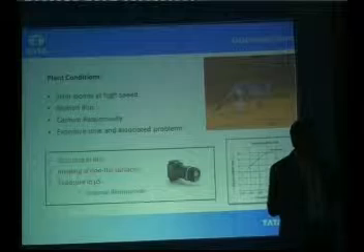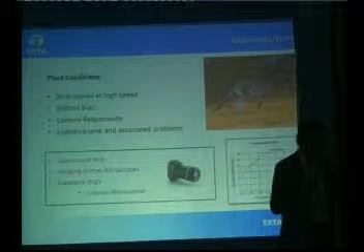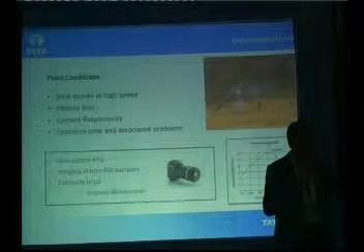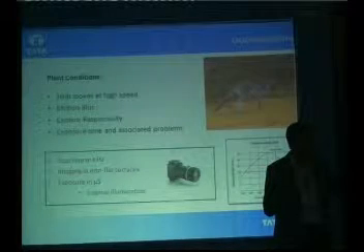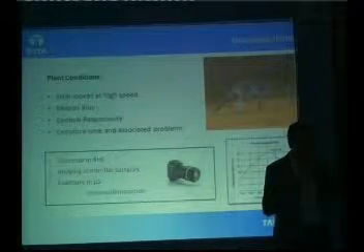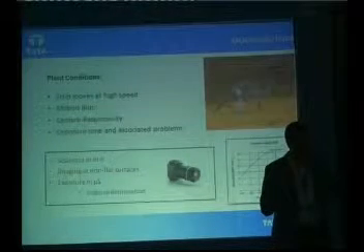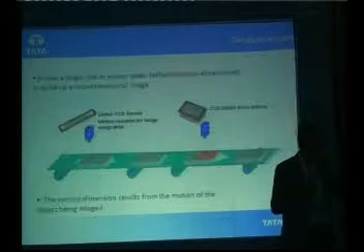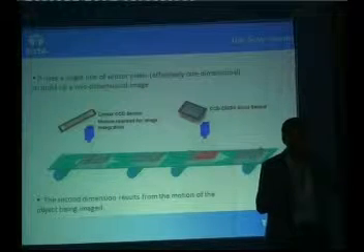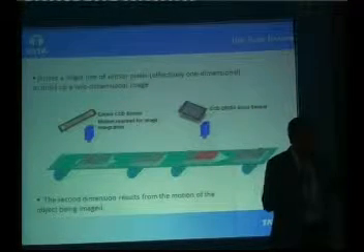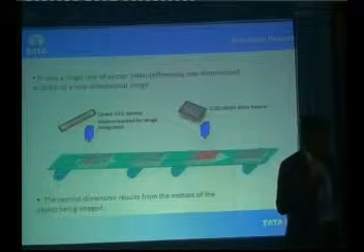So we thought of using a special type of camera known as a line scan camera, where the frequency of scan is in kilohertz. It can image on rollers, which are a very predominant structure in any steel plant. It can image non-flat surfaces, and the exposure time is very low, so as to keep the blur at a minimum. A line scan camera is basically a single dimensional sensor, and by virtue of the motion of the object, it produces a two-dimensional image.